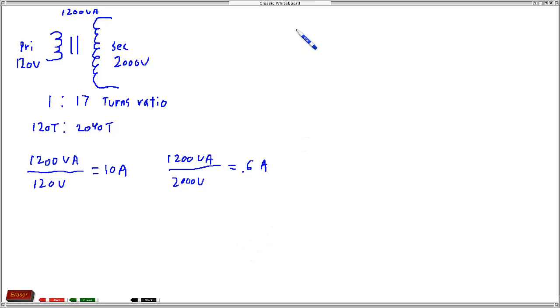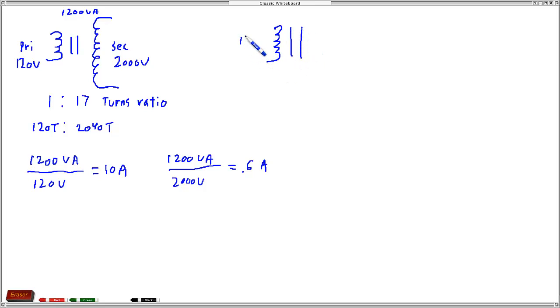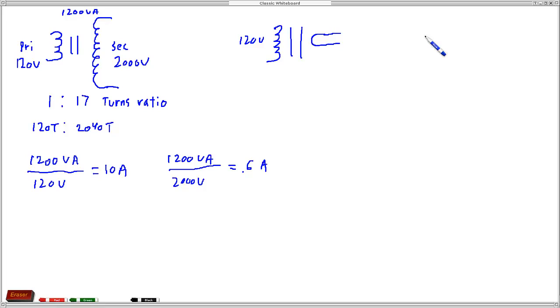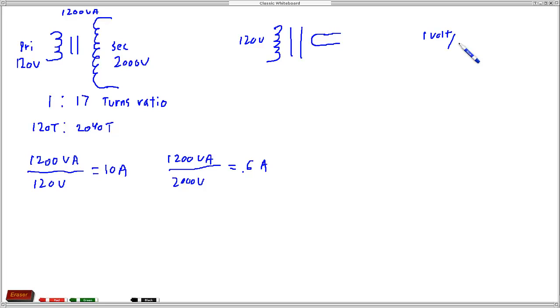When we modified this transformer, what we essentially did was we had on the primary these windings coming in and we know that was 120 volts. And what we did is we added a single turn on this side. Now there's a couple things we know about the transformer. We have a rating of - you can do this experimentally - and you find out that you roughly have a volts to turn ratio of one to one. So you have one volt per turn.